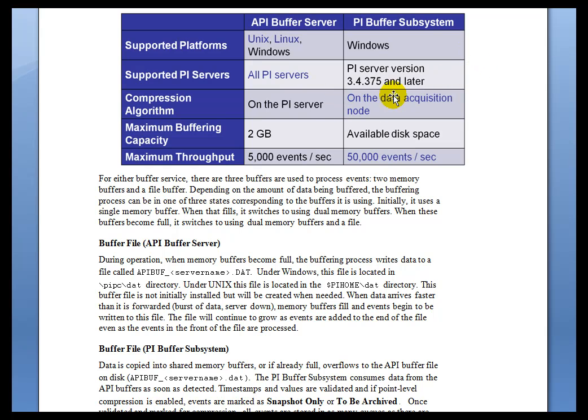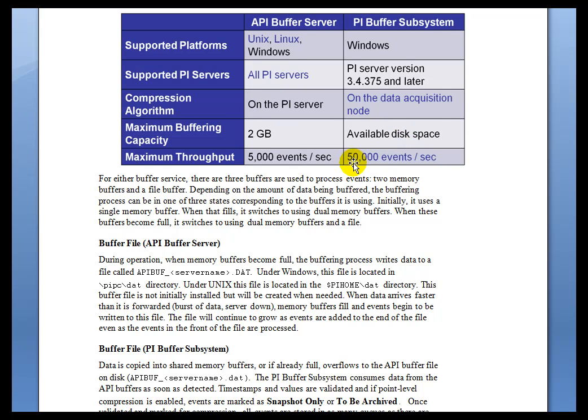From the point of view of advantages — one versus the other — the PI Buffer Subsystem does require a more recent version of the PI Server. If you're running an older version, the API Buffer Server is your only choice. The PI Buffer Subsystem does the compression test on the Interface Node, has no two-gigabyte buffer size limit like the API Buffer Server, and has a much bigger throughput channel.